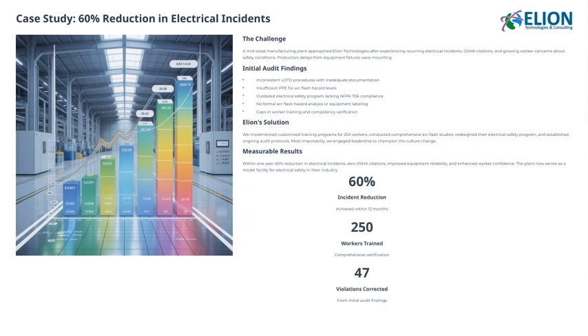We also identified and corrected 47 violations found during our initial audit, which included issues like inconsistent lockout/tagout procedures, inadequate PPE for arc flash hazards, and outdated safety programs that didn't meet NFPA 70E standards. The challenge was clear: recurring electrical incidents, OSHA citations, and increasing worker concerns about safety, all leading to production delays from equipment failures. Our approach was tailored to address these specific issues. We redesigned their electrical safety program, conducted detailed arc flash studies, and established ongoing audit protocols. Importantly, we involved leadership to foster a culture that prioritizes safety.